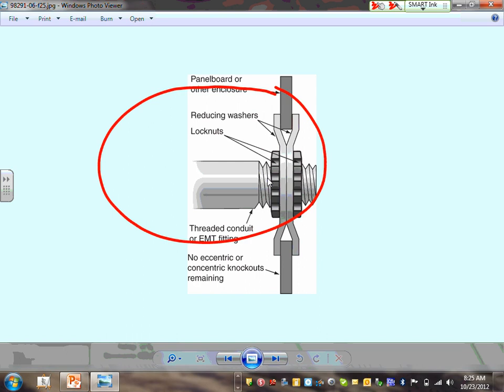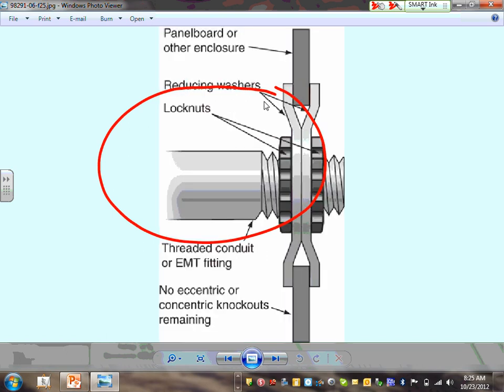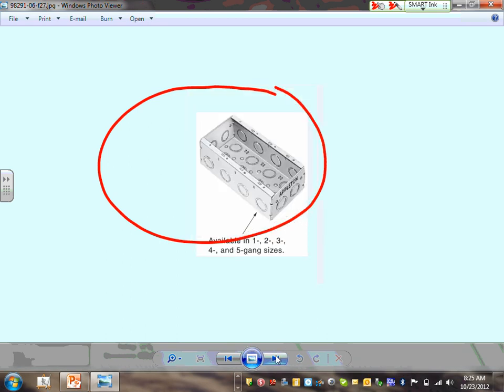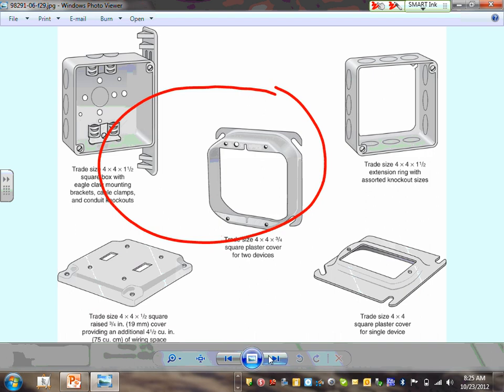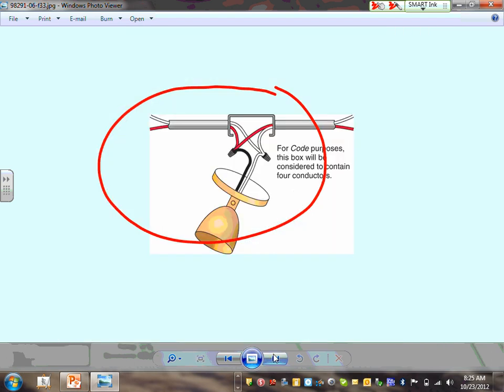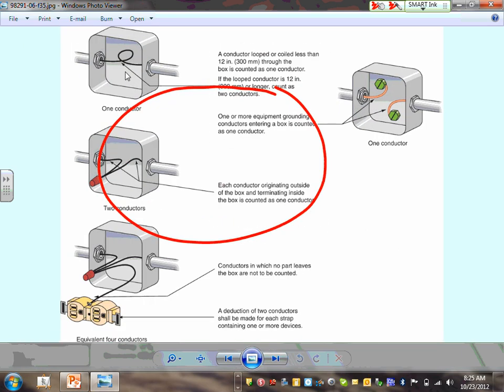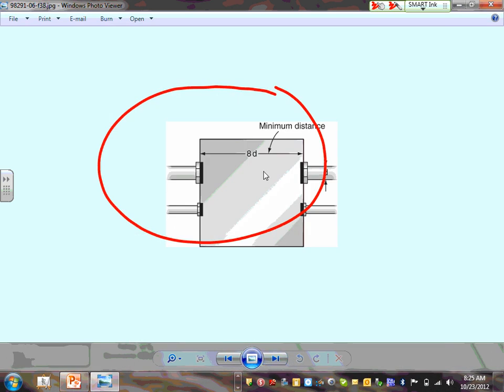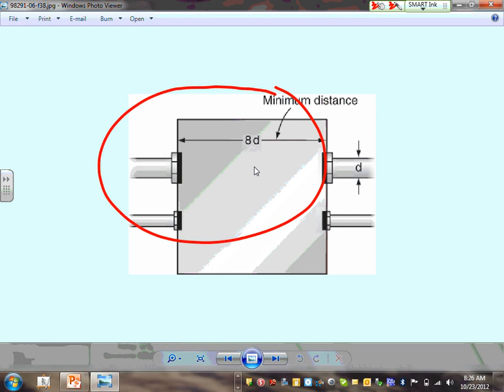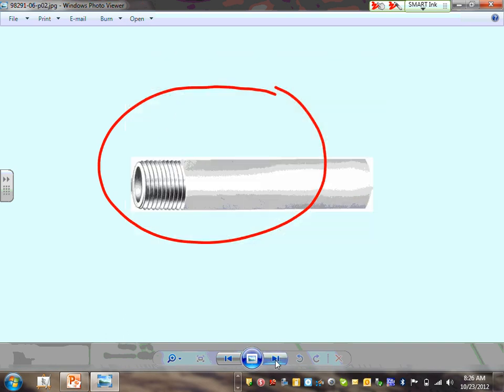Here's where you can use a reducer washer - it reduces a big hole to match a smaller conduit. The rest of the material covers device boxes and different types of handy boxes with fittings. Box fill calculation examples are provided; please read them in the code. Pull box: this becomes a pull box the minute you bring conductor number four or larger into it. Once that happens, certain calculations are required to size that box - we'll do examples for it.